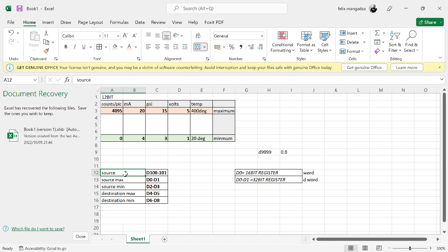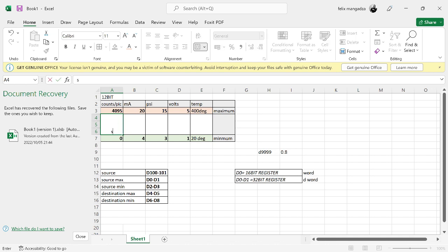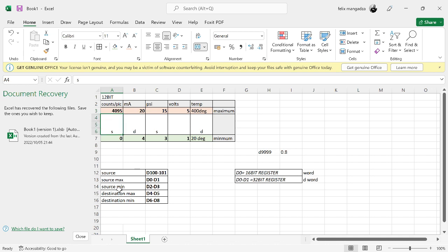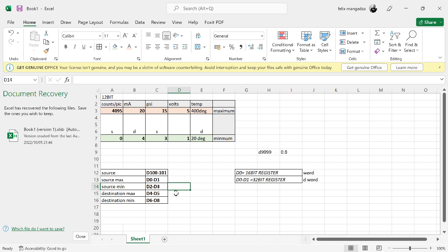These are your instructions. Your source is where your signal is coming in to the PLC. Your source max and source min are your range for the input devices. When I'm converting from this to this, this is the source and this is my destination. If I'm converting from counts to milliamps, this is my source; this is my destination. The source is this data from 0 to 4095. Source maximum is this value. My source minimum is this. The destination is what I'm converting to — so if I'm converting to temperature, this is the destination minimum and this is the destination maximum. I've already assigned my devices here.